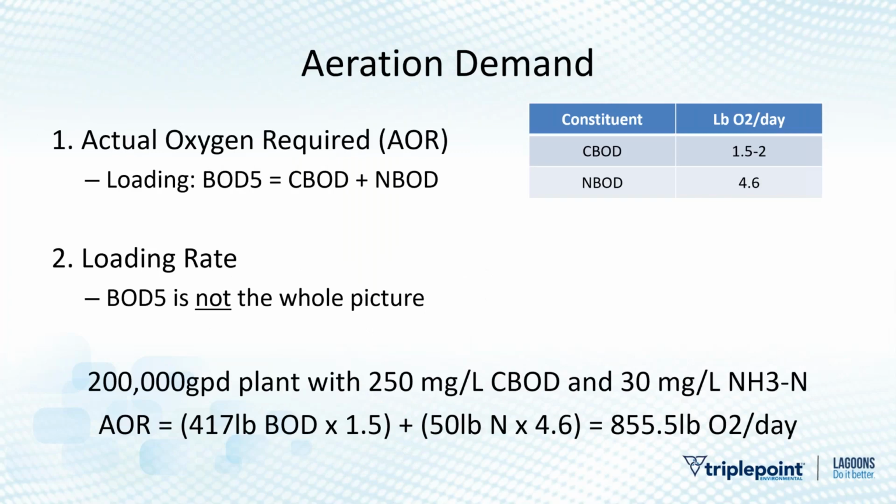So the first one is air demand. And the key one here is AOR. This is what we chase in most of our designs. What is the oxygen required for your lagoon? And the biggest impact or contributors to this is BOD, but BOD5 is not necessarily comprehensive.